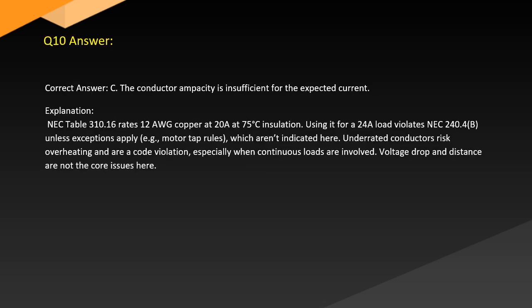Answer. Correct answer: C. The conductor ampacity is insufficient for the expected current. Explanation. NEC Table 310.16 rates 12 AWG copper at 20 amps at 75 degrees C insulation. Using it for a 24 amp load violates NEC 240.4(B) unless exceptions apply, e.g. motor tap rules, which aren't indicated here. Underrated conductors risk overheating and are a code violation, especially when continuous loads are involved. Voltage drop and distance are not the core issues here.